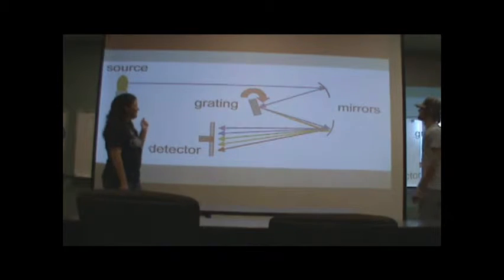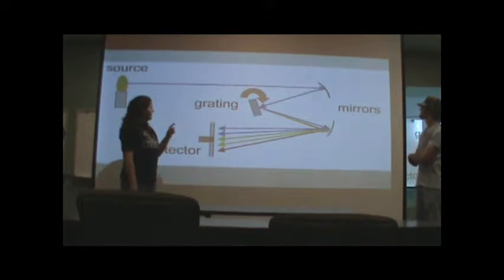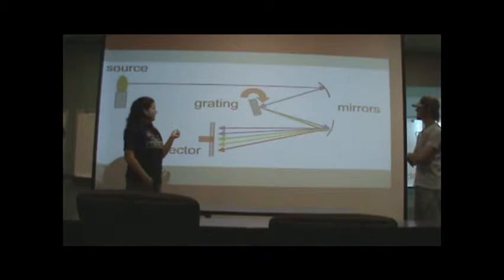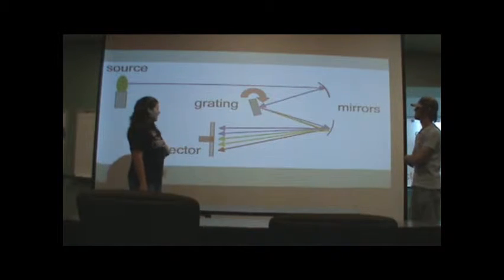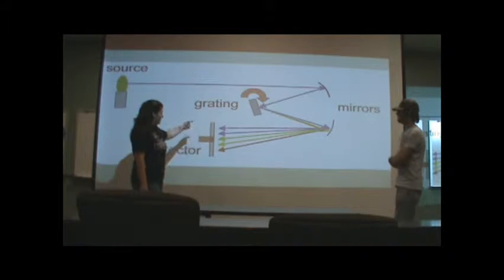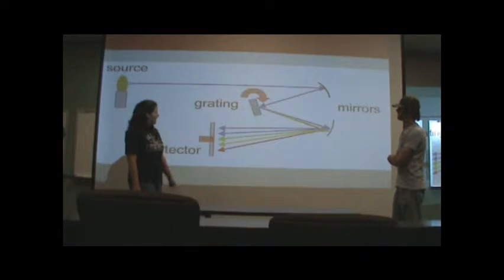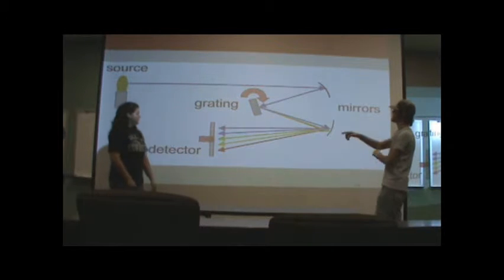The light source is passed through an entrance slit where it hits a concave mirror, and then that light is reflected onto the grating, which diffracts the light, and then it hits another concave mirror, and as it exits, it's even more diffracted, and so you can actually pass different wavelengths by adjusting the grating through the detector.